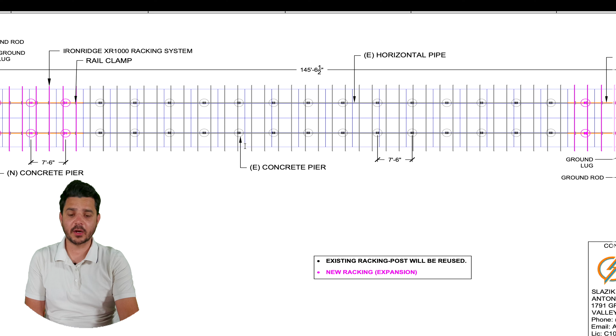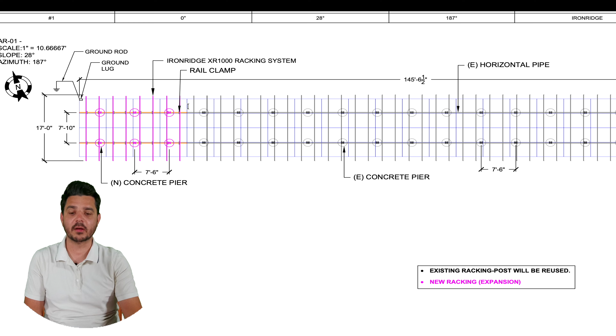We already have the concrete piers in place, and we'll add those in. We've got ground lugs, and we're using Iron Ridge XR1000, specifically their extended rail. They have 2 lengths in the XR1000: a 17 plus foot one and a 16 foot one. By going with the 17 foot 10 inch rail, we can do 4 modules without any bonding or splicing of rails, which helps consolidate cost and keep things uniform. It's great that Iron Ridge offers this with the XR1000, which is strongly recommended for a ground mount system.